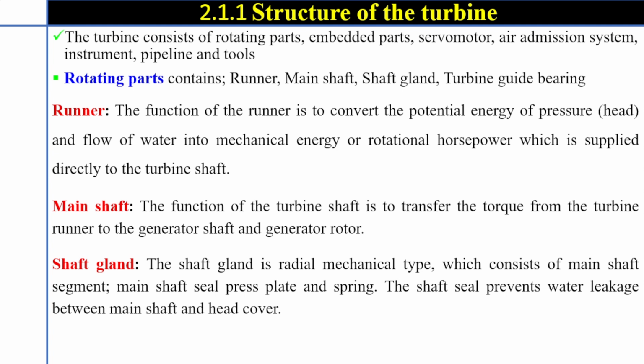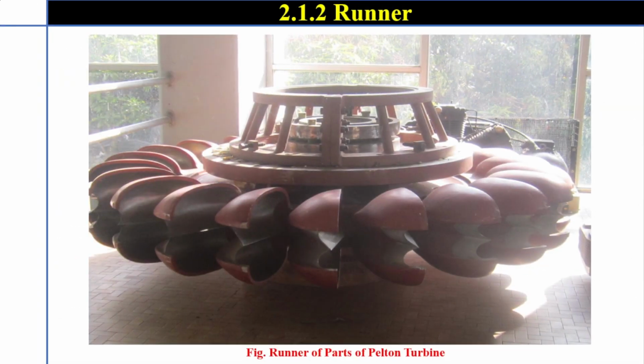Runner. The function of the runner is to convert the potential energy of pressure or head and flow of water into mechanical energy or rotational horsepower, which is supplied directly to the turbine shaft. Main shaft. The function of the turbine shaft is to transfer torque from the turbine runner to the generator shaft and generator rotor. Shaft gland. The shaft gland is a radial mechanical type, which consists of main shaft segment, main shaft seal, press plate, and spring. The shaft seal prevents water leakage between the main shaft and the head cover. This is the runner of a Pelton turbine.